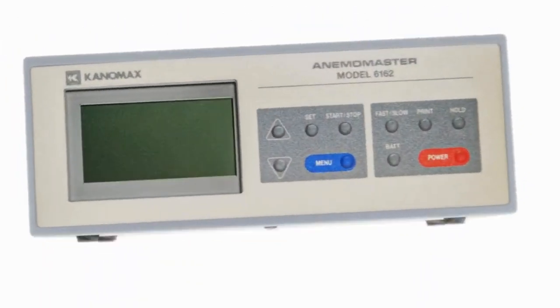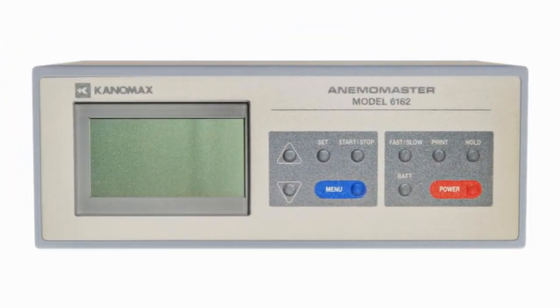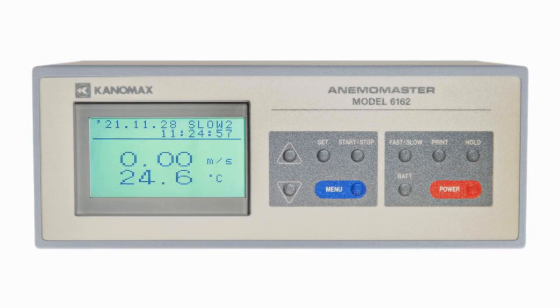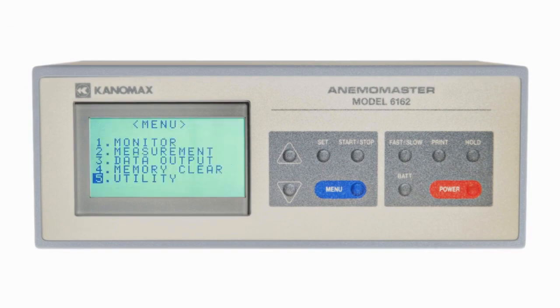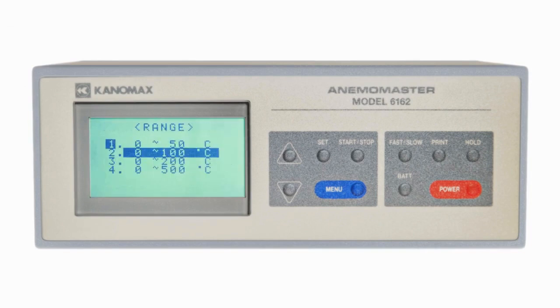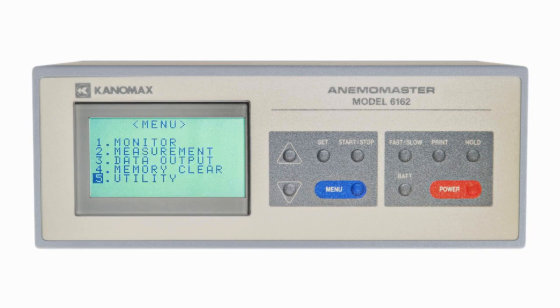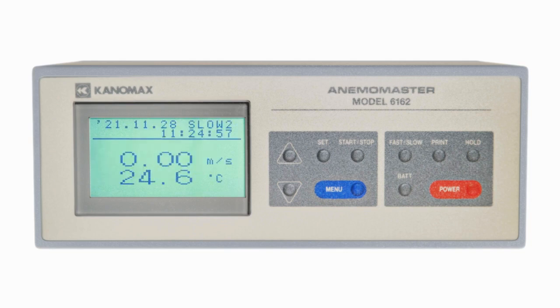If you're using the analog terminals for your measurements, make sure you're getting the output ranges you want for air velocity and temperature by adjusting them in the analog output section of the menus. Once you've picked the range you want, you can press the menu key to return to the menu screen, and press it again to return to the monitor screen.